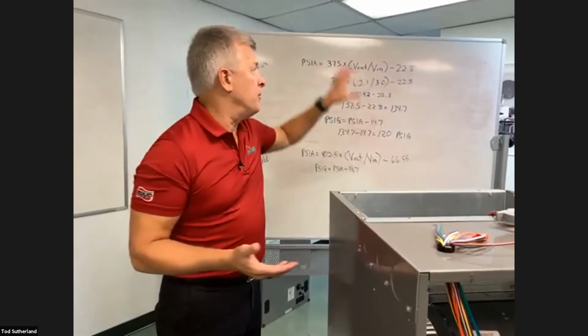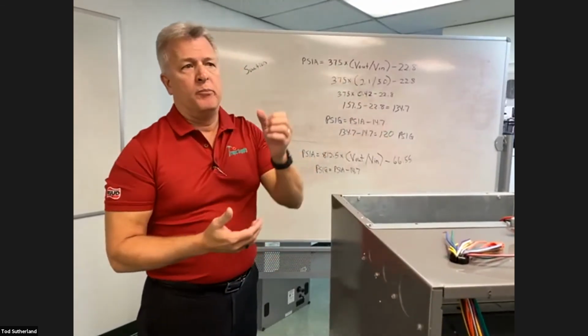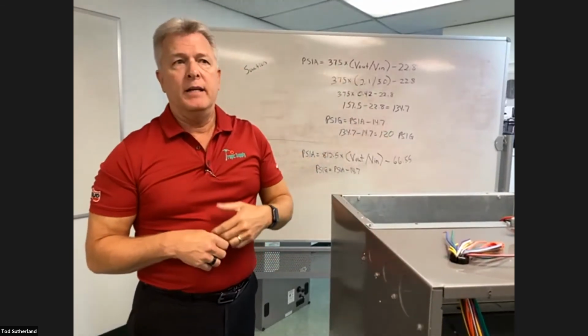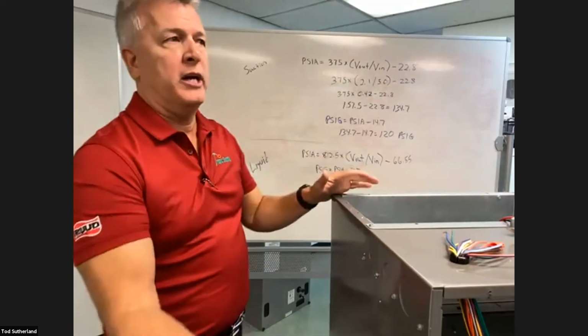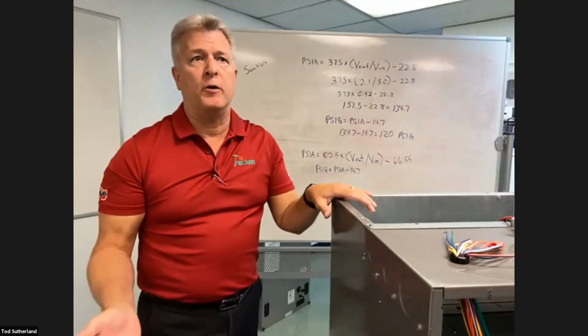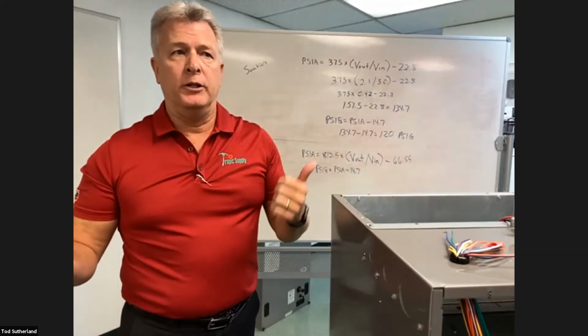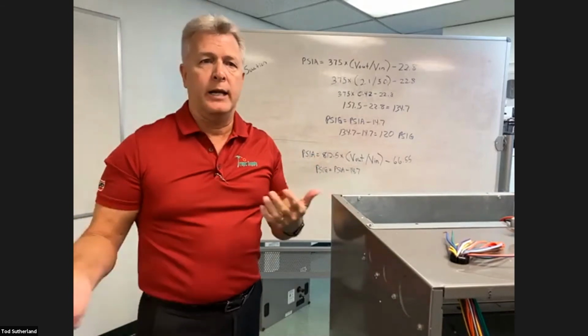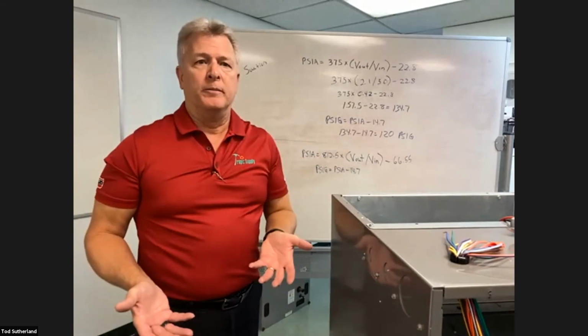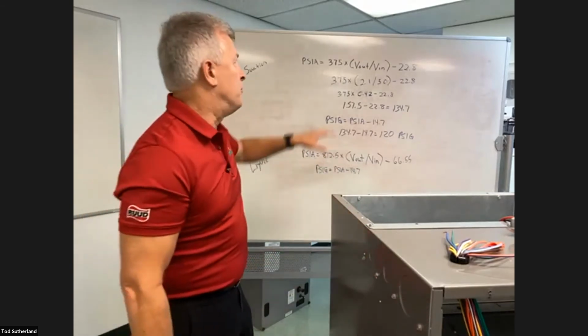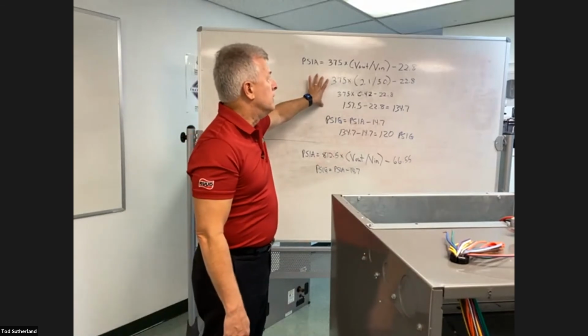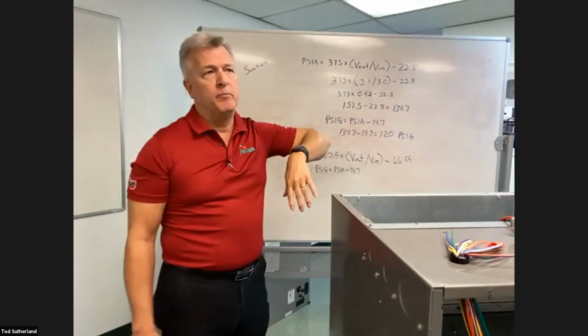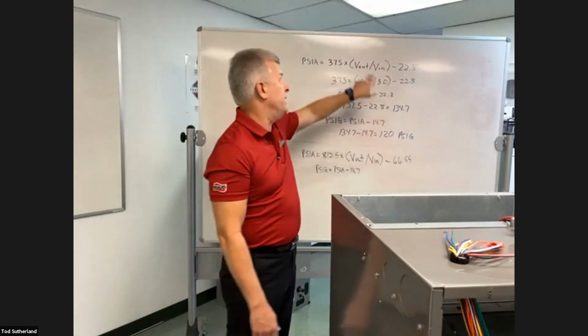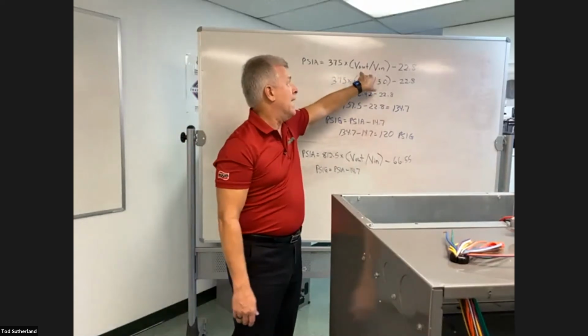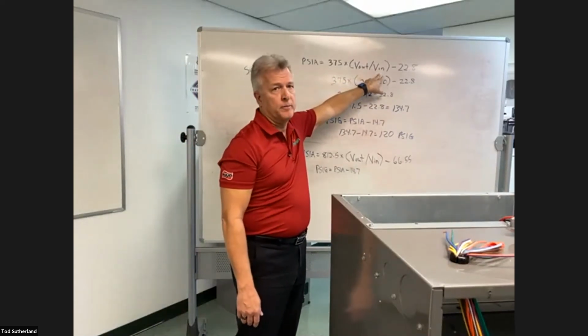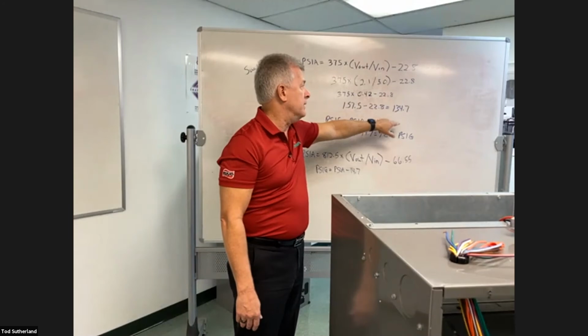Okay, so what this formula is calculating is the pressure of the line. So even if the system's not running, there should be pressure in that line. If the system's been off for a while and the valves are open, you should have an equalized pressure between your liquid line and suction line, but you're still going to have pressure. So you're still going to plug it into this formula. The power needs to be to the unit so you can read your DC voltage going out of the transducer and into the transducer. But the formula is going to be the same.